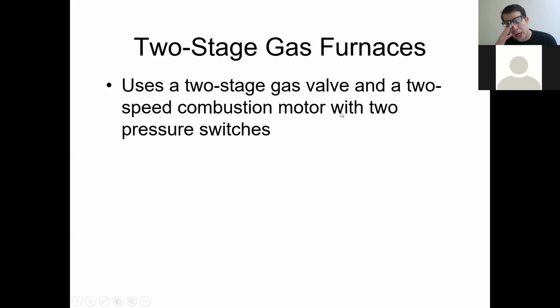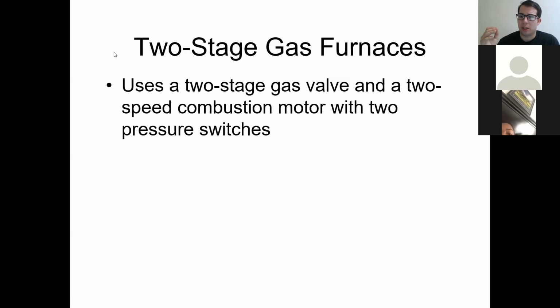So two-stage gas furnaces, this was one of the earlier forms of controlling gas flow and making it so we had a modulation of some sort. It wasn't able to modulate truly. Modulation is we can go from 0 to 100, and we can go 1% at a time, basically, as far as the increase of speed, the increase of heat production. It's just incremental, little 1%, 1% added on at a time.